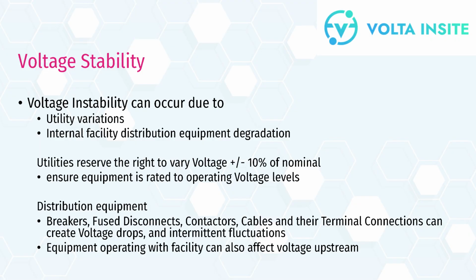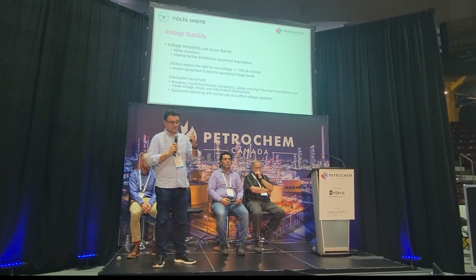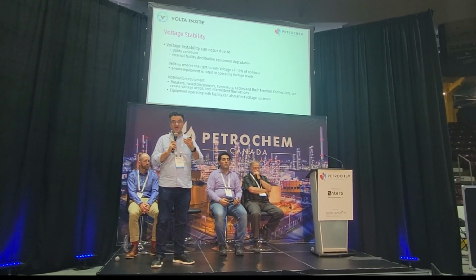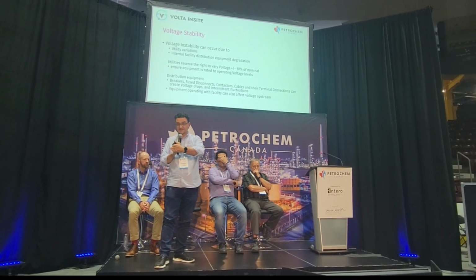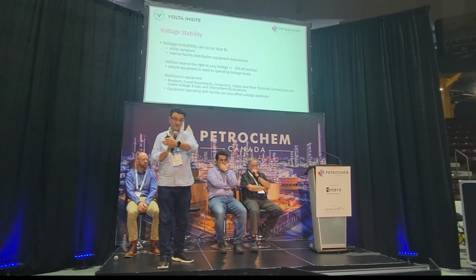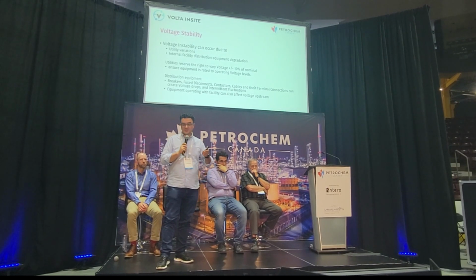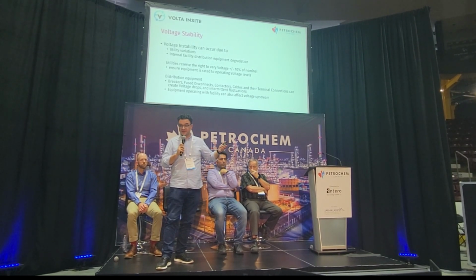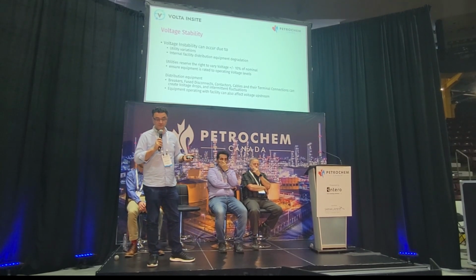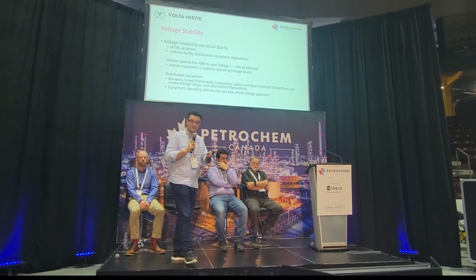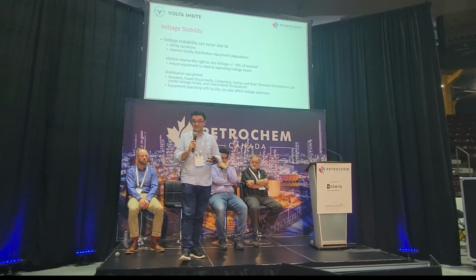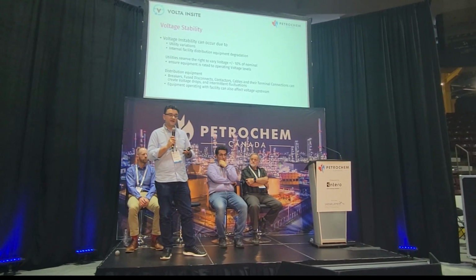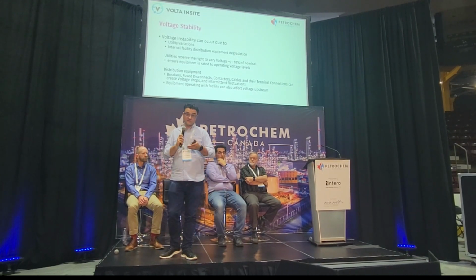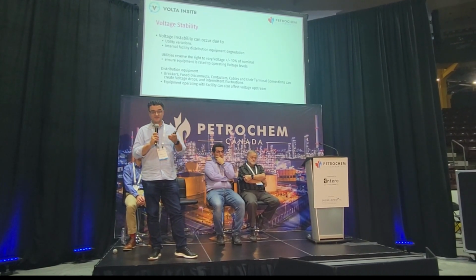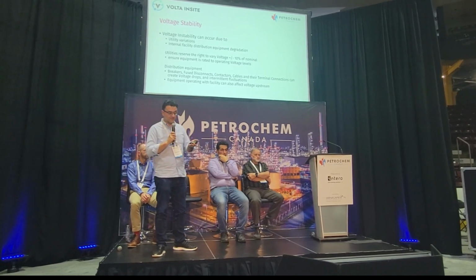On voltage stability, maintaining a steady voltage at all times is important. There are 2 ways that you may have a voltage problem at a particular load where you're actually using that voltage to do work. One is a utility variation that happens, and that's completely outside of your control. The other is within your internal distribution system, you may have something that's acting up, like a fuse disconnect, a breaker that's bouncing, and those are things that you can actually look at and understand and try to eliminate before they become problematic.